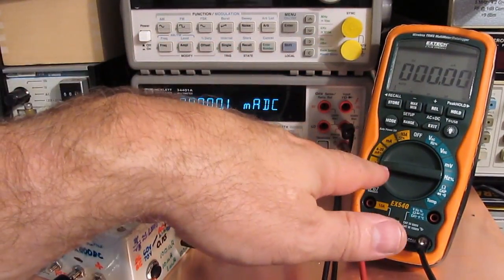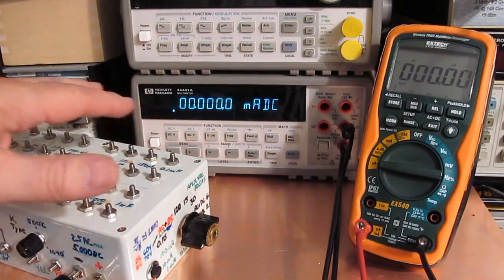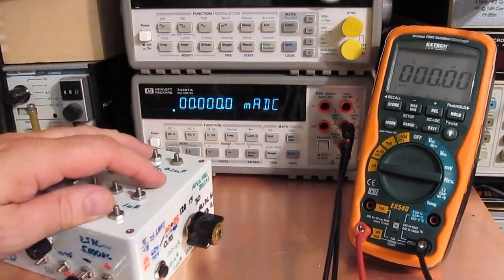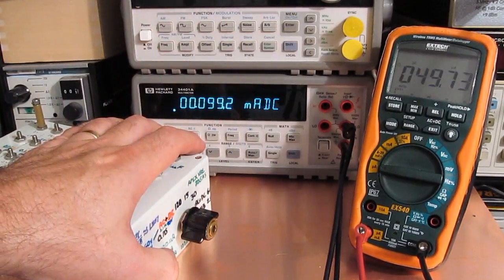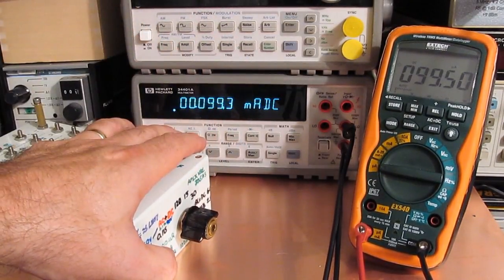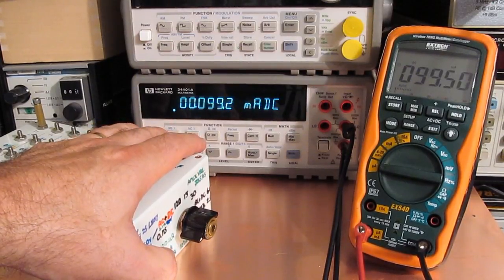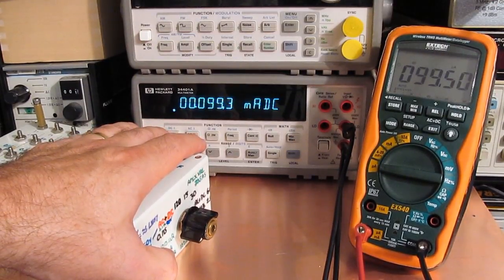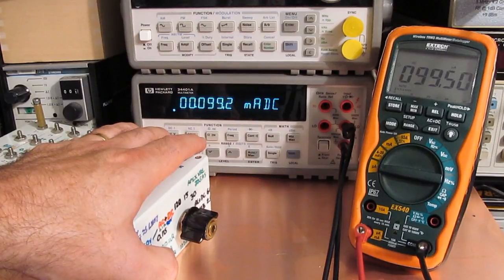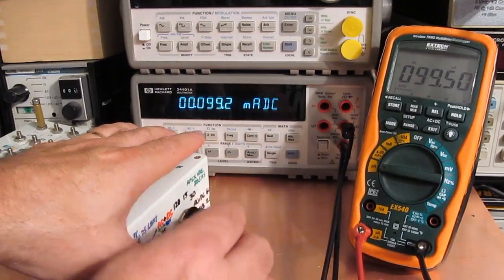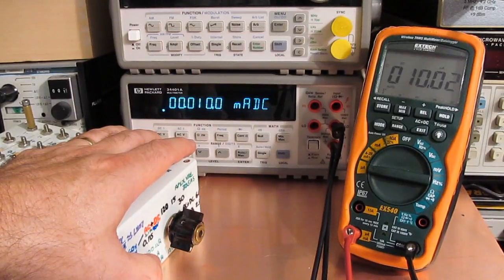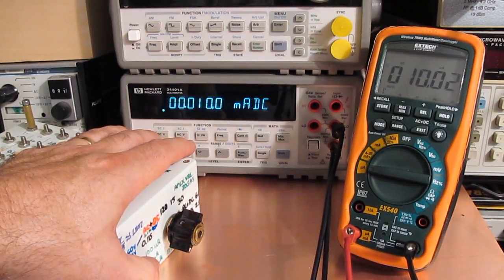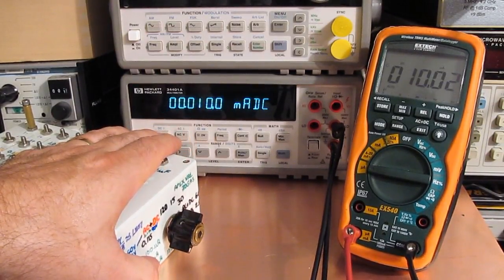You can see I have the Extech set to its microamp range and I've just got them attached to my test box here. Let's start by injecting 100 microamps. You can see we are 99.3 or so, 99.2 microamps on the HP versus 99.5 on the Extech. This is with 10 microamps applied and you can see we're 10.0 versus 10.02.